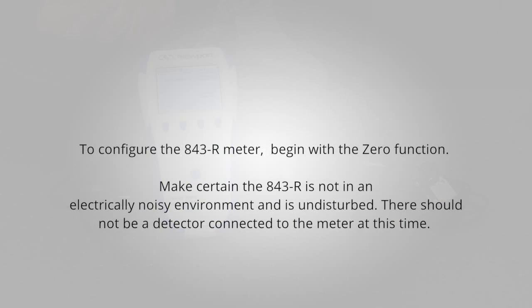To configure the 843-R meter, begin with the zero function. Make certain the 843-R is not in an electrically noisy environment and is undisturbed. There should not be a detector connected to the meter at this time.